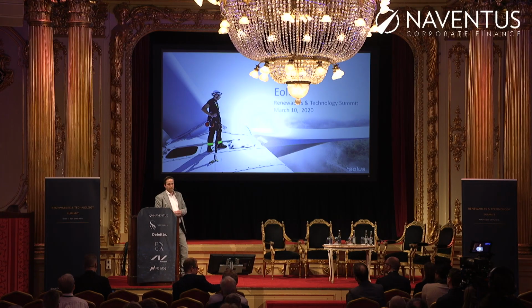Referring to Vestas models, the largest turbines we are building now and will have in operation in 2020 have 150 meter rotor diameter compared to 112 meters. So that means 80% more swept area to harvest the energy from the wind that passes the rotor and convert it into electricity. And of course, that is really one of the most significant drivers for the rapid development of wind and the build out of wind that we see in Sweden, in the Nordics, and globally.